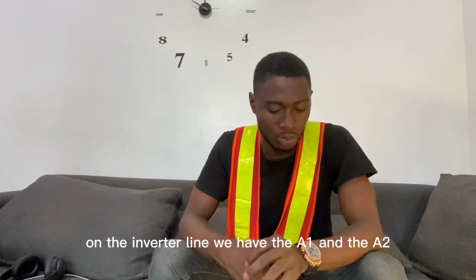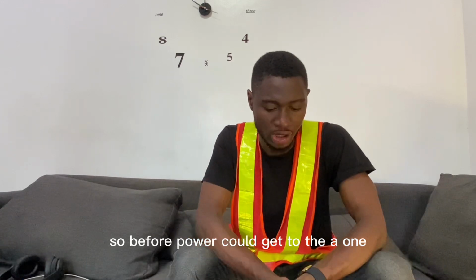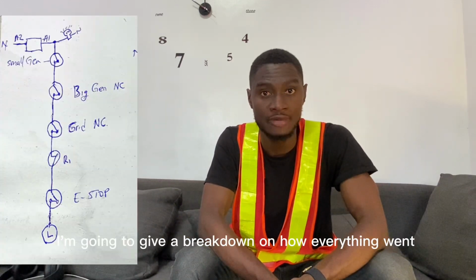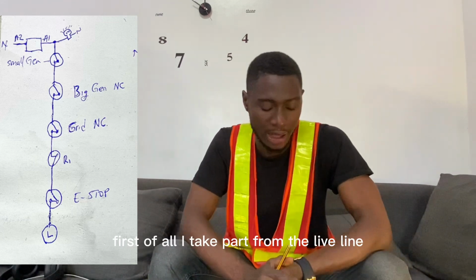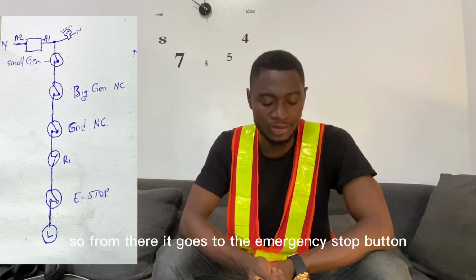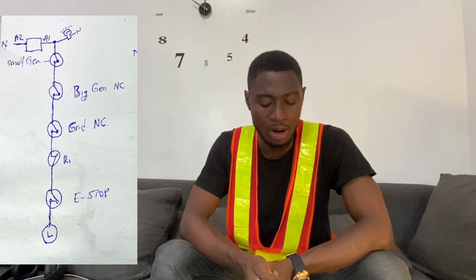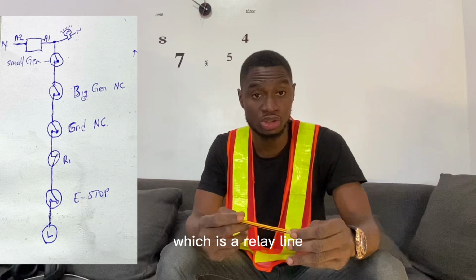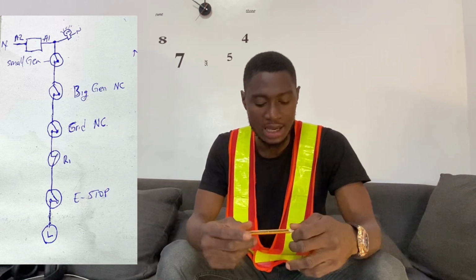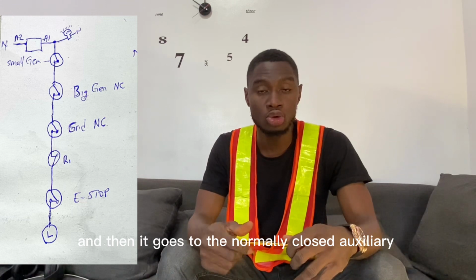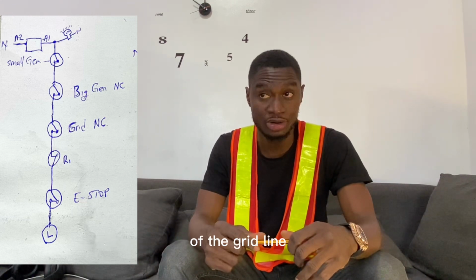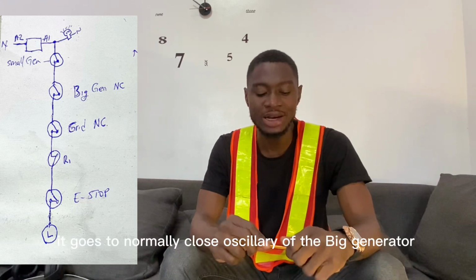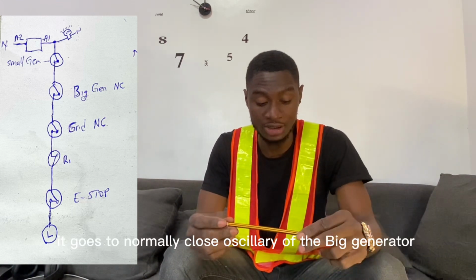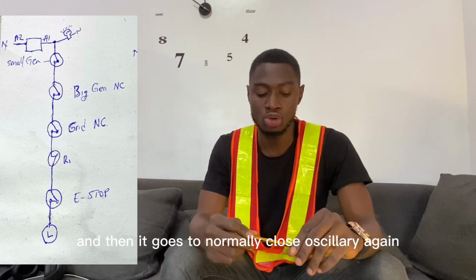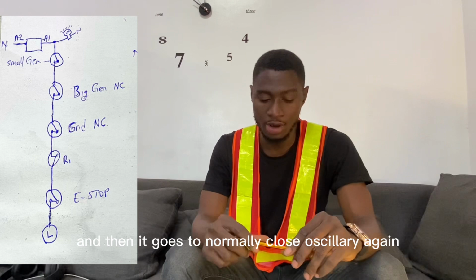I'll go through this again. On the inverter line, we have the A1 and the A2. Before power can get to the A1, I'm going to give a breakdown of how everything goes. First of all, I take power from the live line. From there, it goes to the emergency stop button. From the emergency stop button, it goes through R1, the normally closed relay line, and then to the normally closed auxiliary of the grid line. Then it goes to the normally closed auxiliary of the big generator, and then to the normally closed auxiliary again of the small gen.